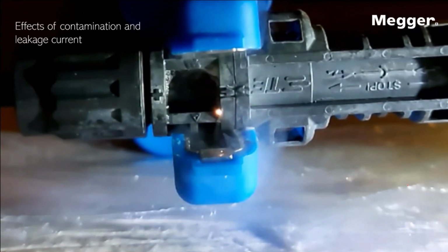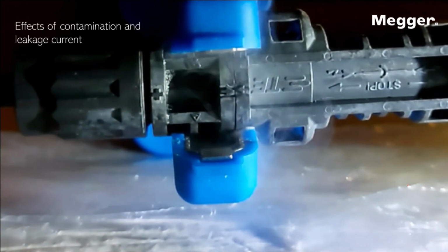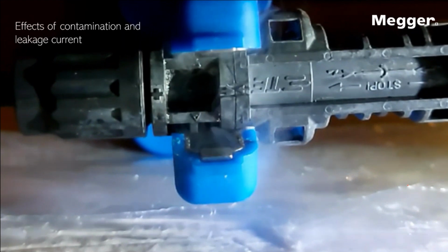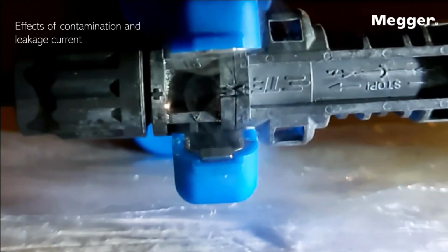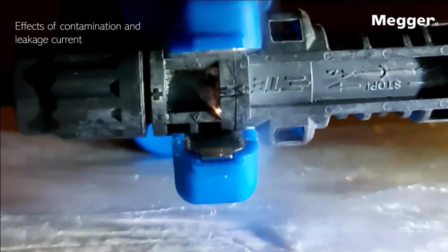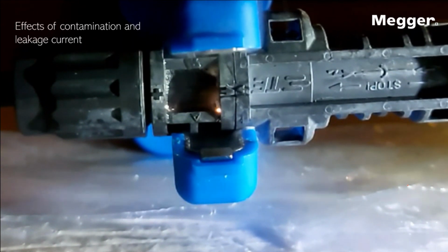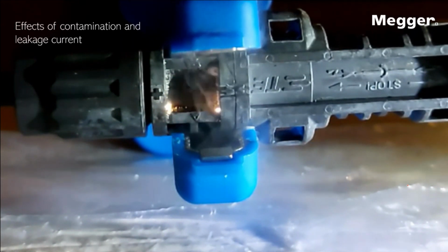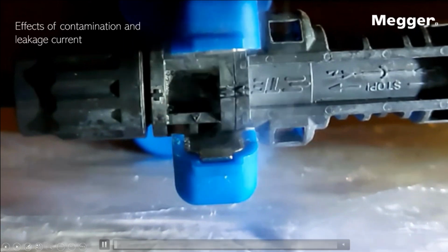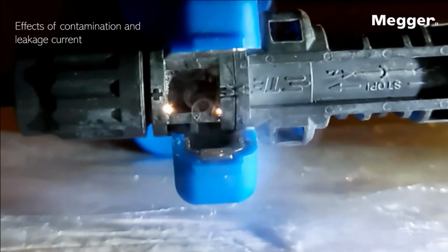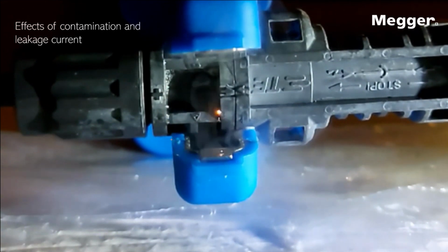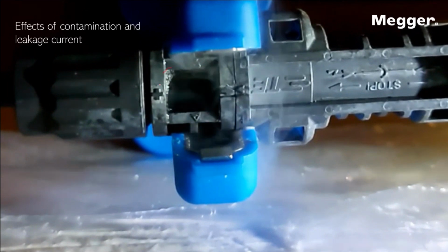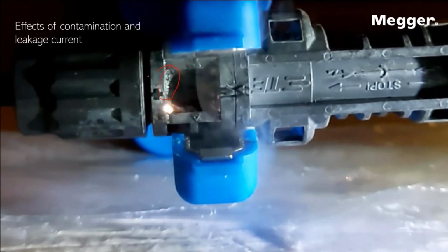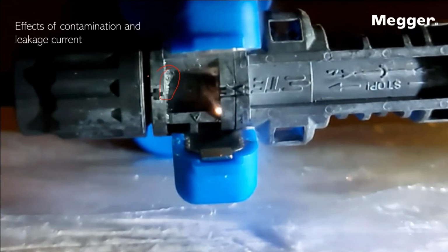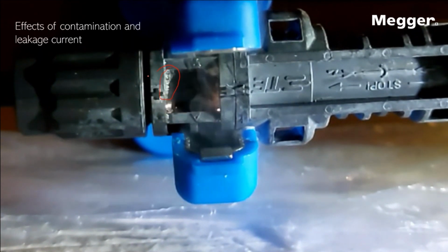Those surface currents definitely can create problems, and you want to at least be sure that you are not influencing your measurement because of a surface current. This quick video shows an example of that, how current circulates due to contamination or a bad connection. Actually, you can see moisture here. That can create a path, and that can give you a bad result.